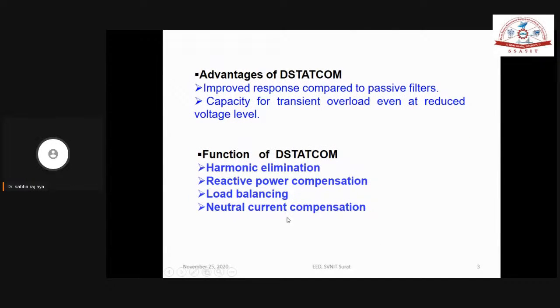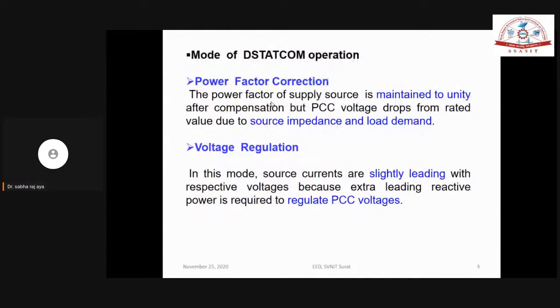So again, the advantage, which we have first discussed. Main advantage: dynamically you can compensate. If our leading reactive power is high, this will supply lagging reactive power. If lagging reactive power is high, this will supply leading reactive power. Dynamically, this converter is going to adjust its property. And it has capacity for transient overload, even during low voltage also.